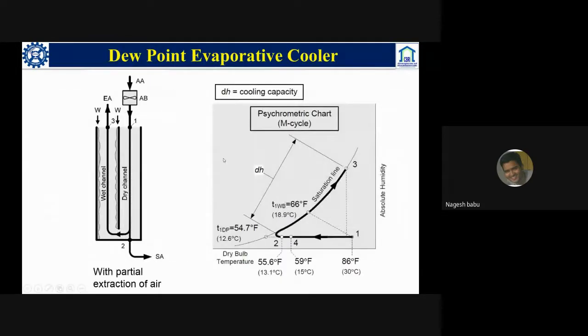Then there is another type of cooling, that is dew point evaporative cooling, in which we can not only reach towards the saturation line, but we can go towards the dew point line. The dew point is what you observe in the nights around 2 or 3 o'clock, when we can observe a lot of fog. So dew point is a condition where we almost achieve fog. So without a compressor, with a single evaporative cooler, we can go up to dew point temperatures using a dew point cooler. Operating the dew point cooler in this mode, however, the delivery air will be reduced by up to 50% or 60%.